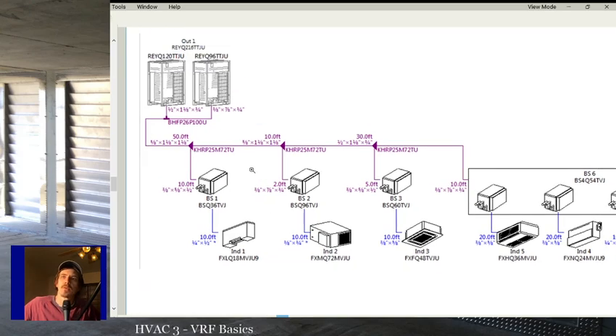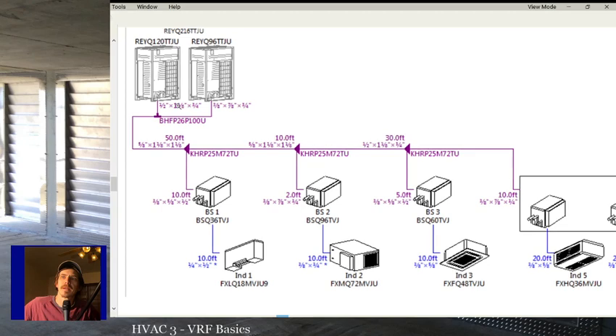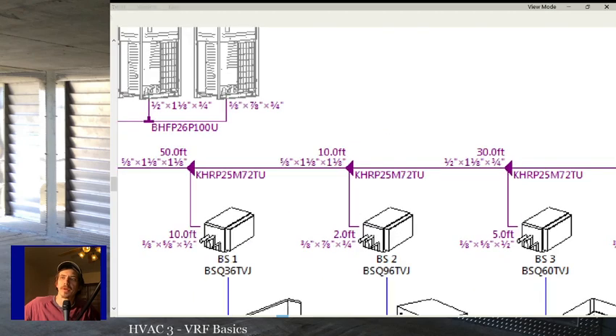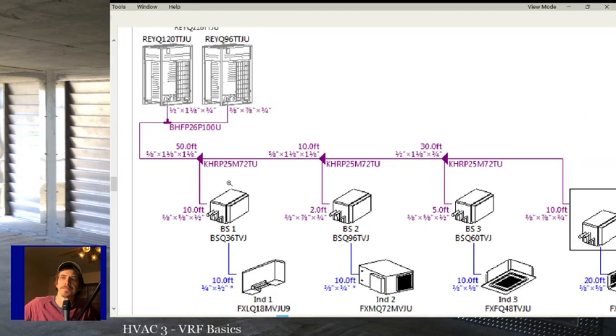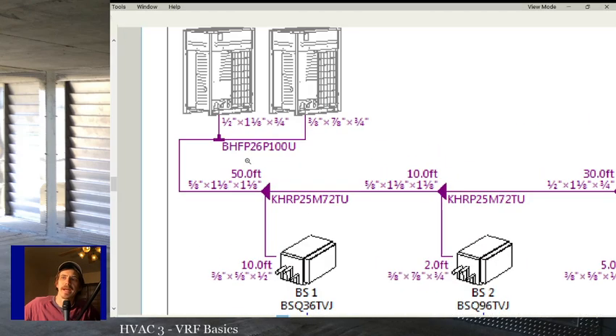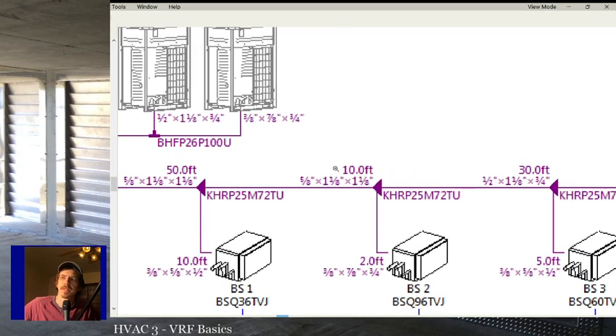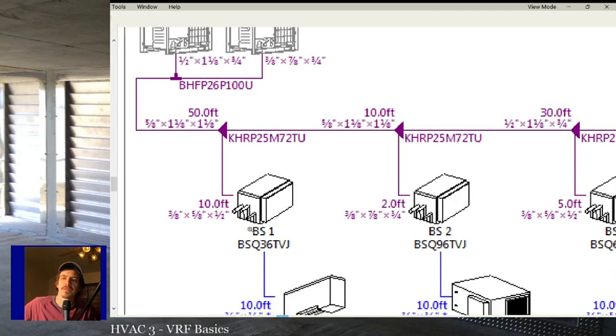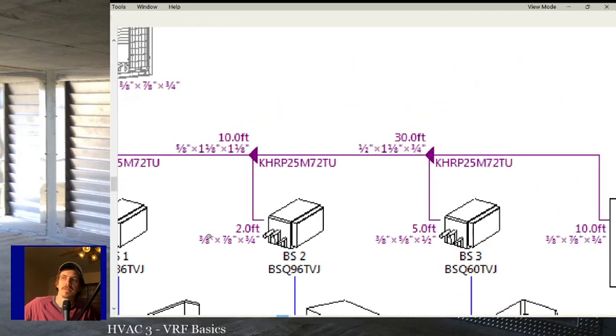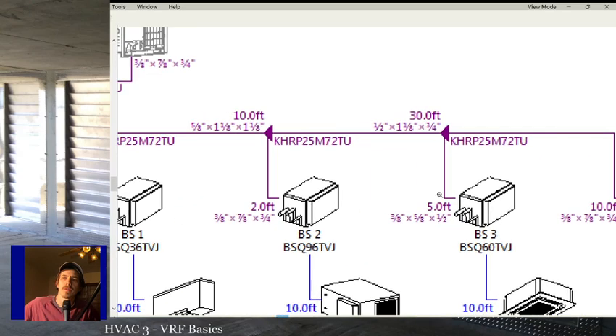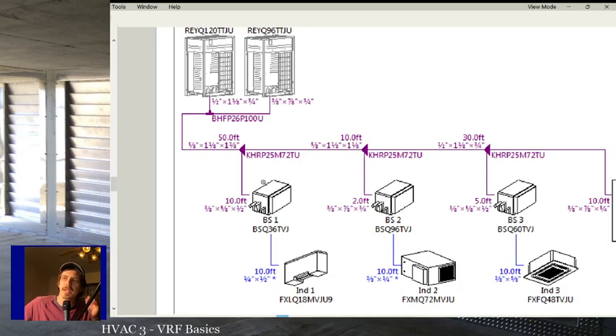The important thing with the piping on this is that if you can see, and I know it's probably hard, if not impossible to see, but if you can see on this drawing, the other thing they have is distances. So it's 50 feet here, it's 10 feet here, it's 10 feet here, it's 10 feet here, and so on and so forth. What they're showing on these piping diagrams is the distance from Y to Y, right? T to Y, Y to Y.